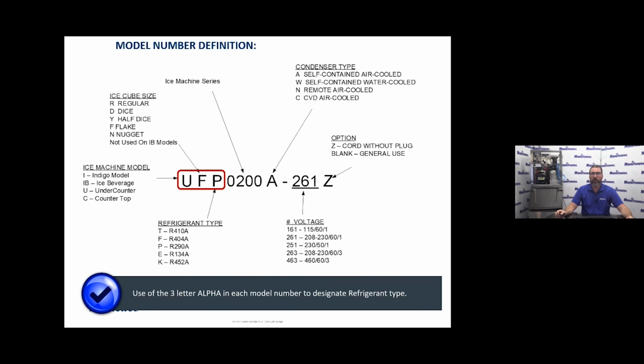If you're on a flake or nugget, if it's an older unit, it's going to be a 404A unit. On some of the newer ones, and what you might see more and more in the future, we're going to be seeing a lot more propane units. After that, we have our series, and that number usually correlates to the approximate capacity per day for that machine in pounds. Then our condenser type, this is a self-contained air-cooled.